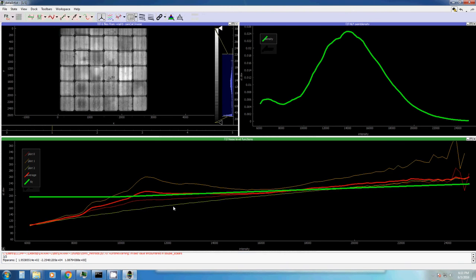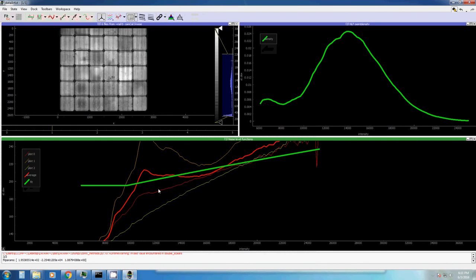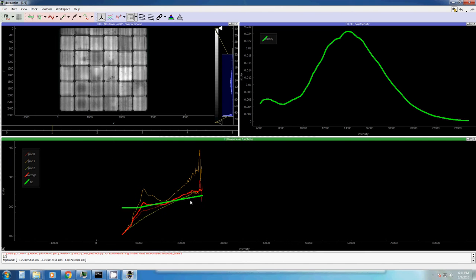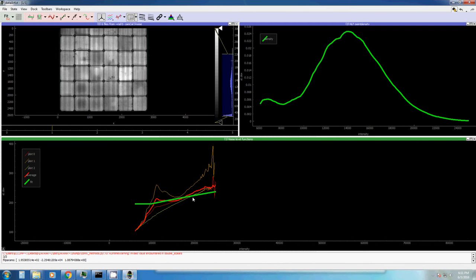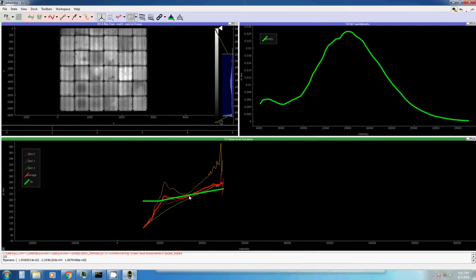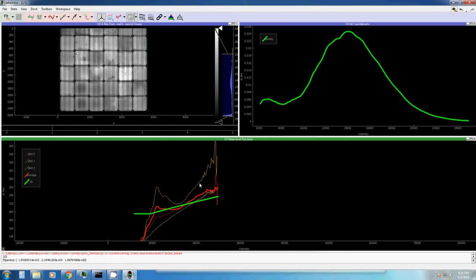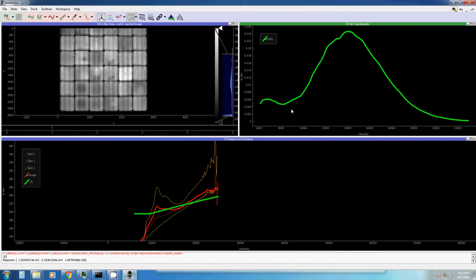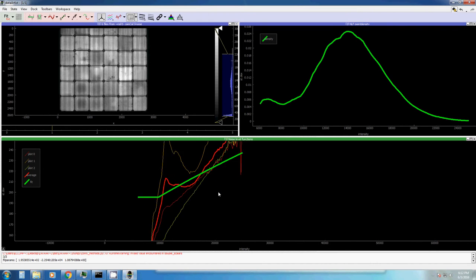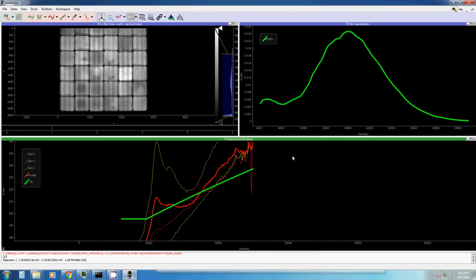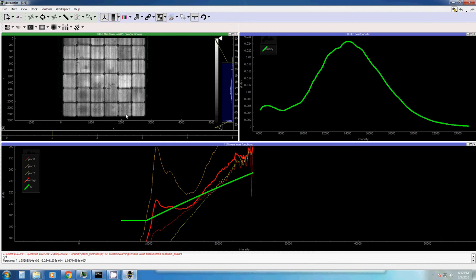Let's activate the noise level function. It takes a few seconds. And it will be faster soon. Here we go. We have our noise level function. So let's look at these plots. What you see here are basically the noise levels for each individual image pair. We have three image pairs, that's why six images in absolute. Then an average value and the fit value. And this display, you see the pixel density. So how many pixels were there at a given value. So knowing now the noise level function of our image is a nice thing because this is one of the calibration parameters that we need. For example, when it comes to single time effect removal.